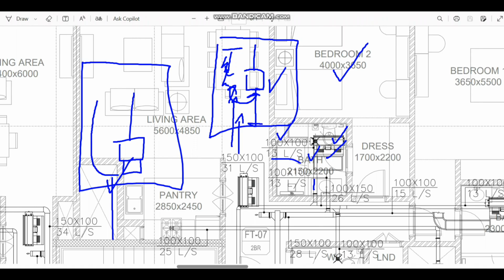But this is not recommended, to keep the fresh air very far away from the FCU. What we normally recommend is like 500 to 600 mm from the FCU. Sometimes okay, 1 meter also okay. But sometimes the client will say a maximum of 200 to 300 mm away from the FCU. You keep the fresh air connection there for proper air circulation. So we have to avoid keeping the fresh air connection 2 meters or 3 meters away from the FCU. That is not acceptable. Try to keep it as close as possible to the FCU for free air discharge. So we normally recommend keeping it a maximum of 500 mm from the FCU.